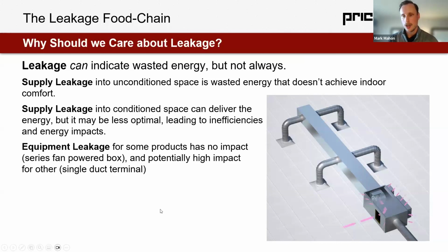Well, we do have to have considerations for the type of equipment we're specifying. So here in the bottom right, we can see a series fan powered box, which has this blower on the discharge of the product attached to the whole integral casing here. Series fan powered box is negatively pressurized. Any leakage that might occur is actually leakage in from the plenum, which frankly, is going to have no impact on our system leakage whatsoever. It's just going to be entrained return air that's already closer to the condition we want it to be. It's not actually going to have a super negative impact because of that. Series fan powered boxes don't have any leakage specification for the casing. A single duct, though, is potentially very high impact. So we're mostly going to talk about single duct VAVs.